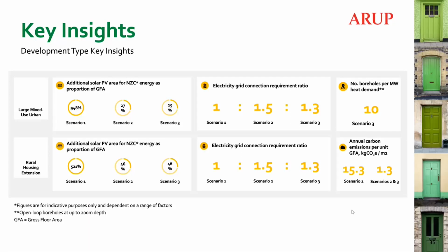Towards the right hand side, for sites with suitable ground and hydrogeological conditions for open loop boreholes, we found that around 10 open loop boreholes were required per megawatt of heat demand to supply the ambient loop network.